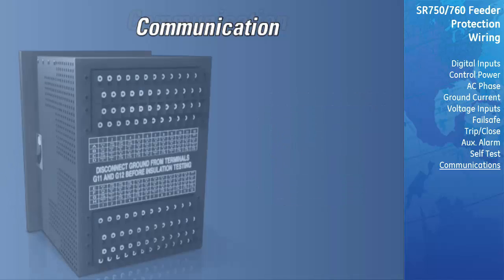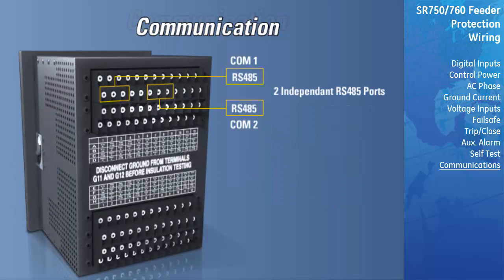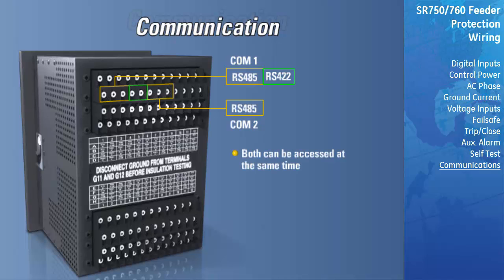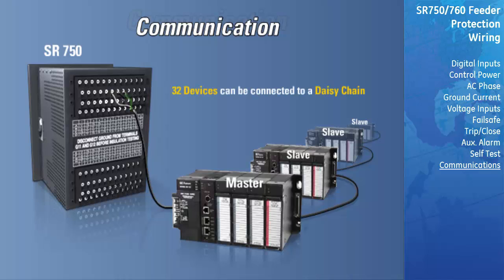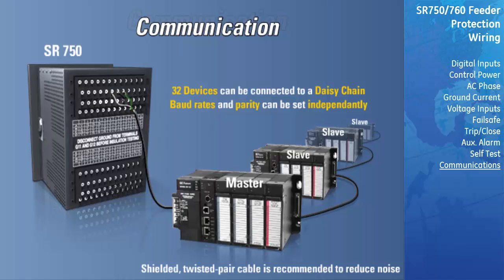The rear communication ports are independent RS-485 ports, with COM1 having the ability to be configured for RS-422 hardware. Both ports can be accessed at the same time and are intended to be connected to a Modbus communication network. A maximum of 32 devices can be connected to a single daisy chain. Baud rates and parity can be set independently for each port. To reduce communication errors caused by noise, shielded twisted pair cable is recommended. The cable should be grounded at only one end, either at the relay or the master device. Terminating resistors and capacitors are also recommended to reduce interference.